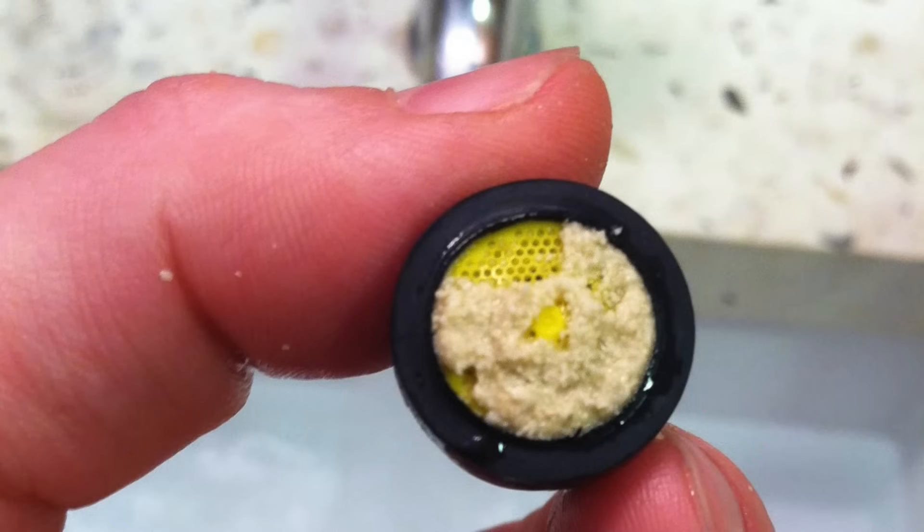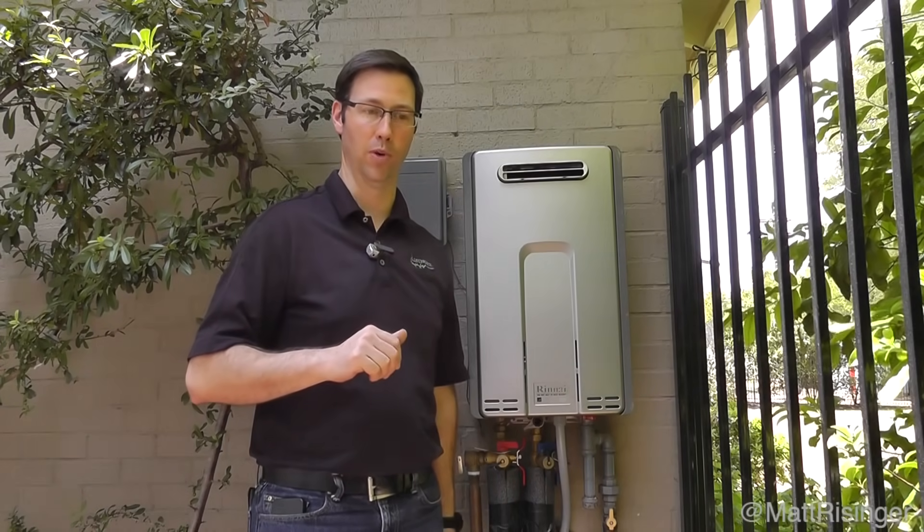That scale is going to throw off into your systems and it makes a mess. I'll lace in a photo of some scale on a house I helped out where we had to take all the aerators off, including the thermostatic valves. It's a mess and a lot of work. You really want to clean these regularly so you don't have any problems.